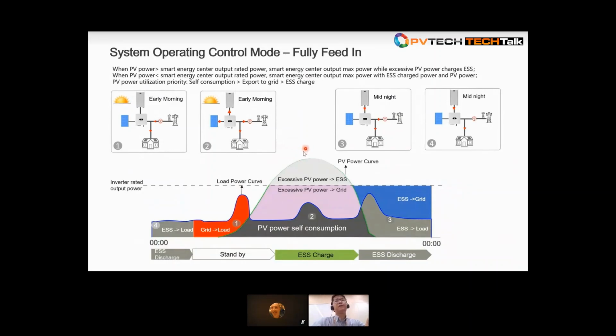Another working mode is fully feeding. In this mode, as I mentioned, it's used for areas with a good feed-in tariff or with net metering. Firstly, your PV power will provide power to the home loads in the daytime. When there is some excess power, it will be fed into the grid. This purple area will be fed into the grid. For this gray area, say we are using a long string design with a 150% DC-AC ratio, this kind of peak power will not be cut and will not be wasted, because we have an energy storage system, so we can charge this excess power into the ESS first. Then under the fully feeding mode, it will first provide power to the load, and then the excess power will be provided to the grid, to make as much money as possible, or to use in the metering mode. So this is fully feeding mode.